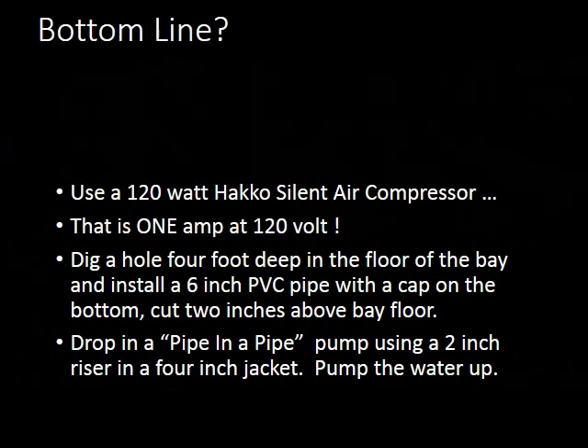The most efficient setup we found uses the 120-watt Hakko silent air compressor — that's only 1 amp at 120 volts. The installation: dig a hole 4 feet deep or deeper, install a 6-inch pipe with a cap on the bottom — that's your wet well — and have it come up about 2 inches above the bay floor. Drop in a "pipe in a pipe" pump. We used a 2-inch pipe with a 1-inch or 1.25-inch inside pipe.